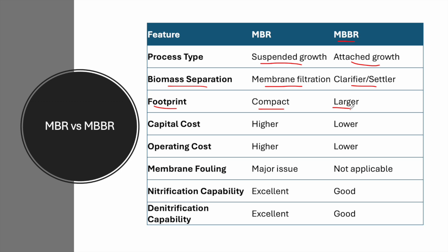We can have very small plants using the MBR. The MBBR also has a small footprint but is somewhat larger than the MBR. Both require less space compared to conventional activated sludge technology, but MBR is the smallest. For capital costs, the MBR is quite expensive — expect a high capital cost. The MBBR is lower in capital cost compared to the MBR, but both have high capital costs.